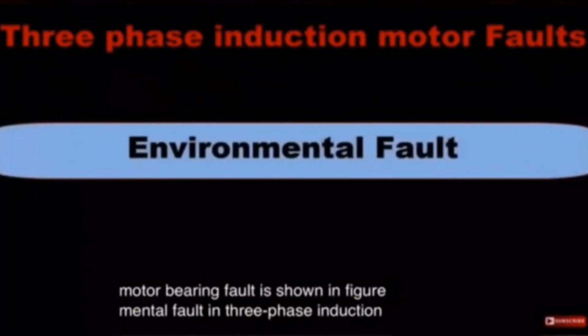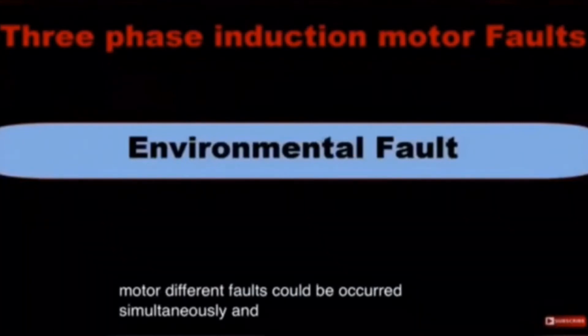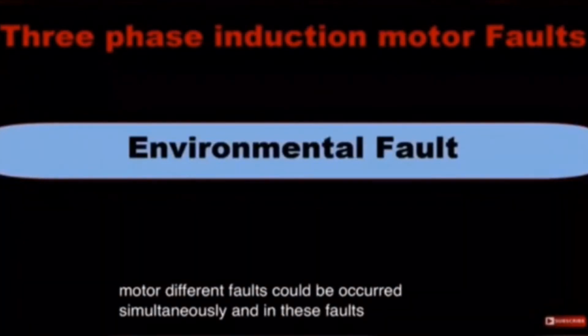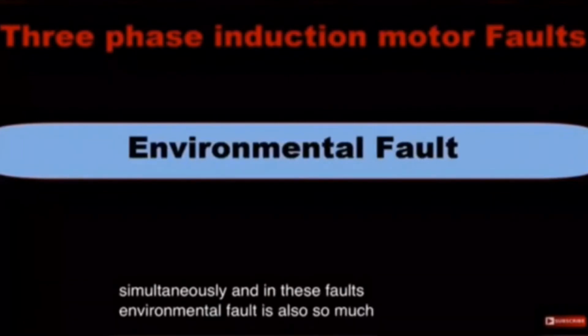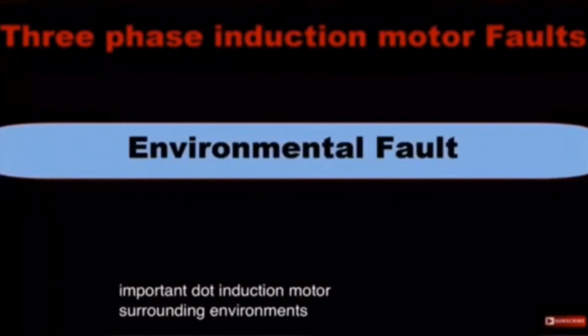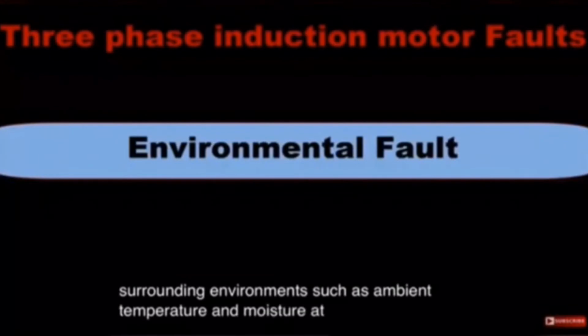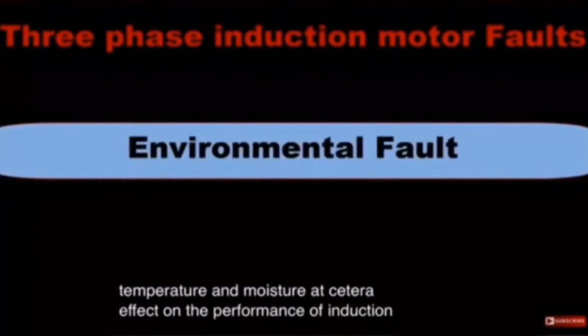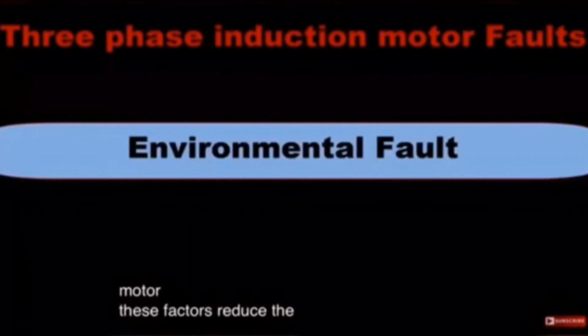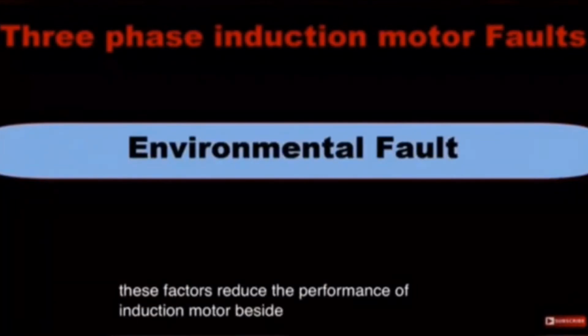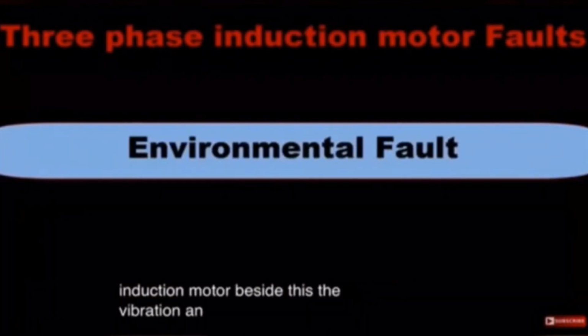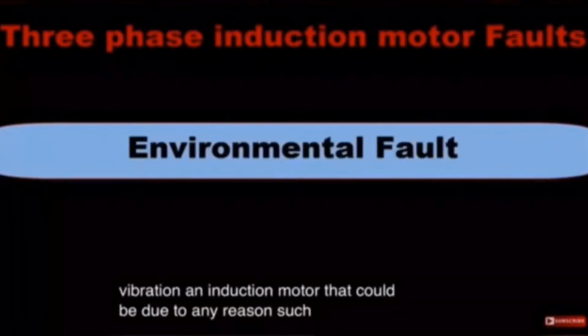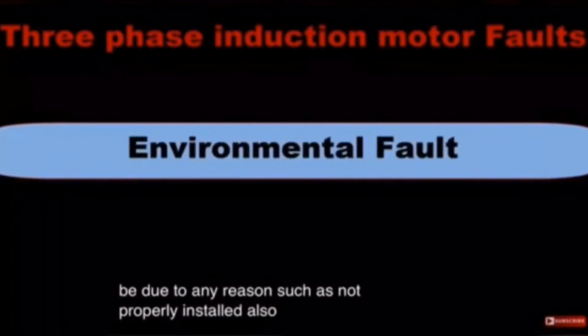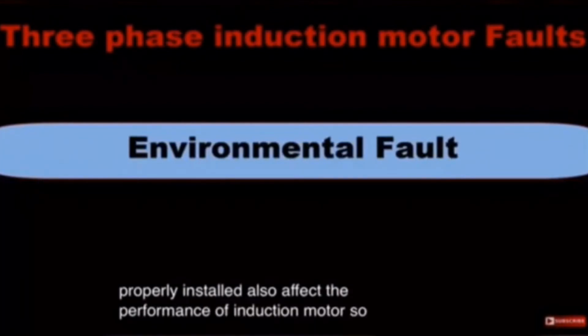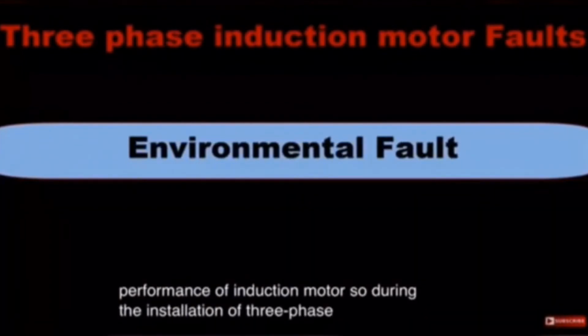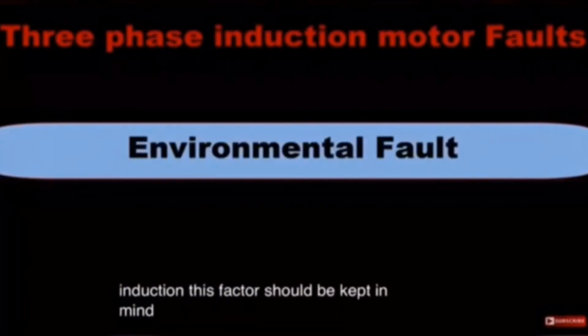In 3-phase induction motor different faults could occur simultaneously, and, in these faults, environmental fault is also very important. Induction motor surrounding environment such as ambient temperature and moisture etc. affect the performance of induction motor. These factors reduce the performance of induction motor. Besides this, the vibration in induction motor that could be due to any reason such as not being properly installed also affects the performance of induction motor. So during the installation of 3-phase induction motor this factor should be kept in mind.